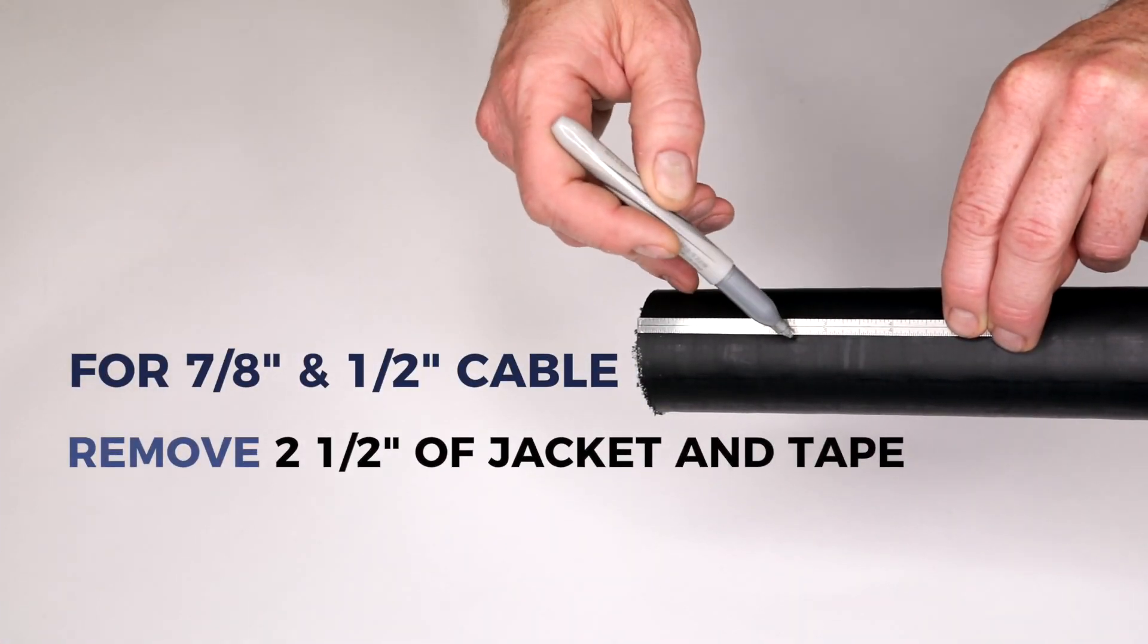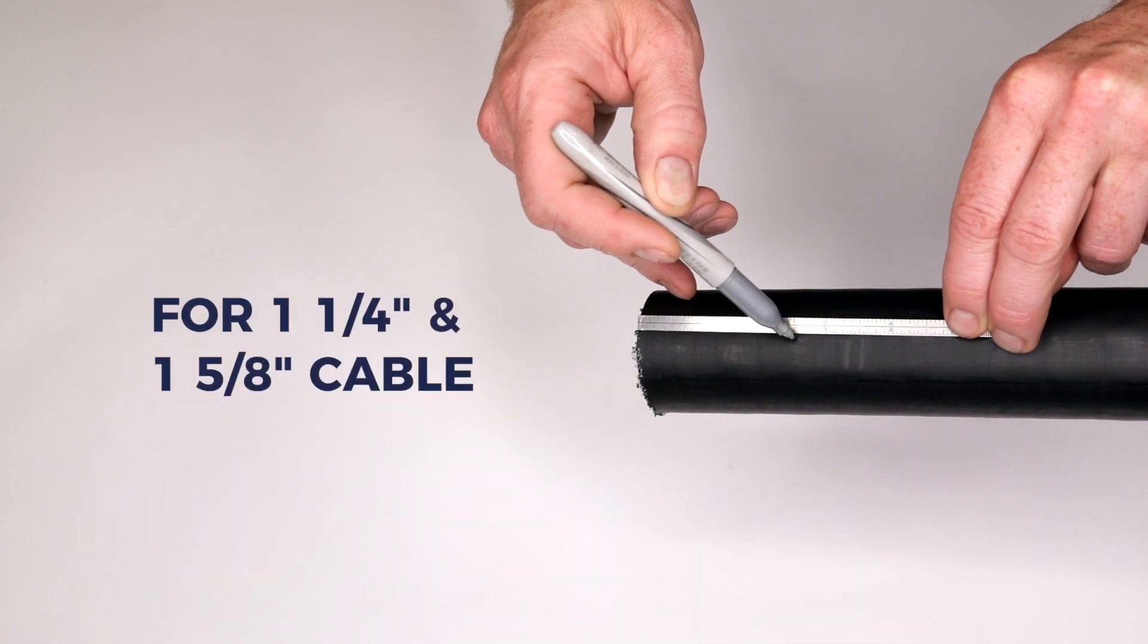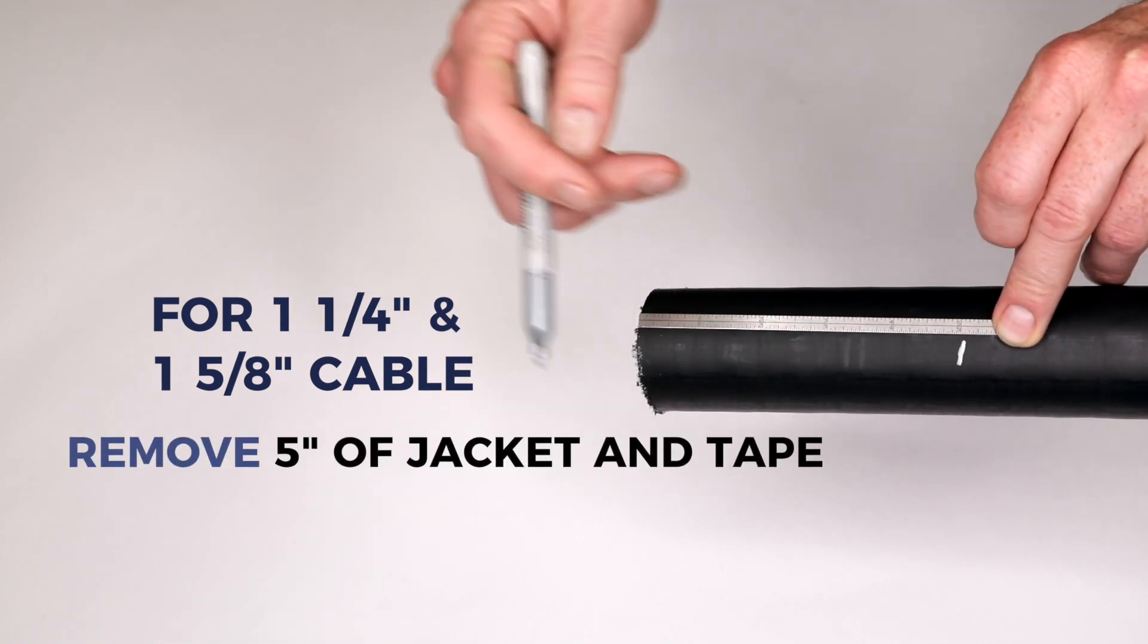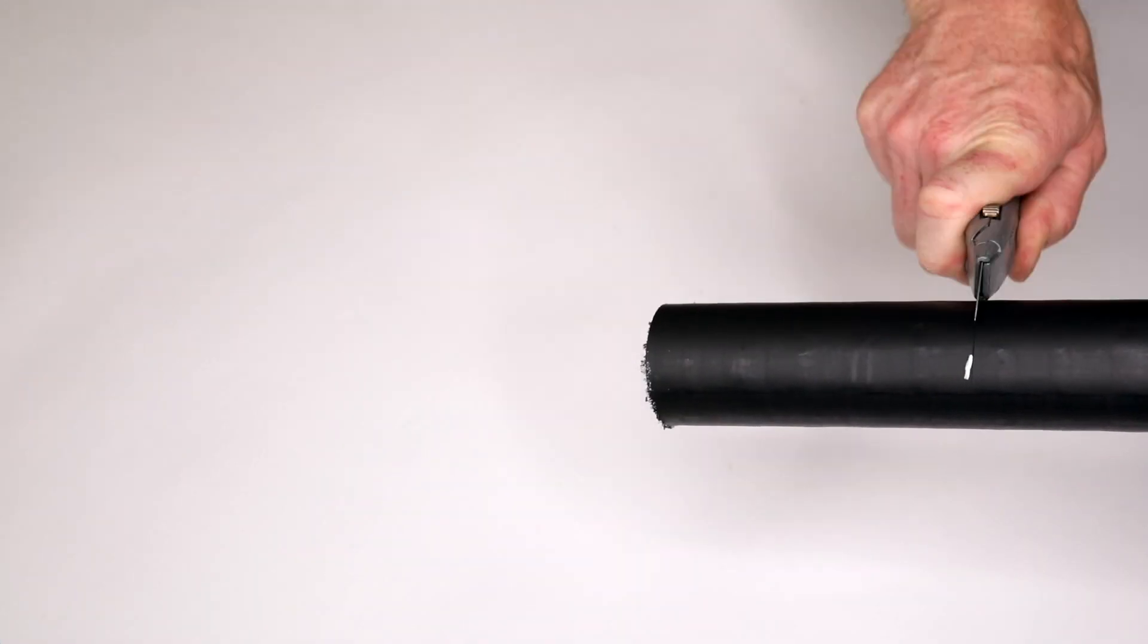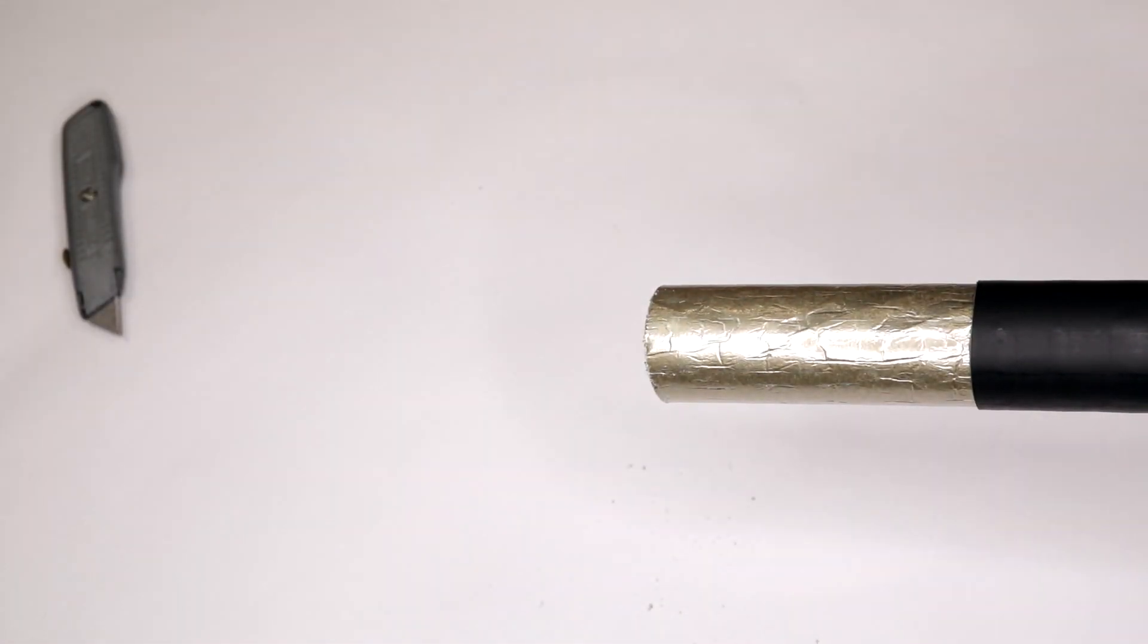For 7/8-inch and half-inch diameter cables, remove 2.5 inches of jacket and tape. For 1-1/4-inch and 1-5/8-inch diameter cables, remove 5 inches. Using a razor knife, remove the jacketing and any tape, making sure not to cut through the outer conductor.